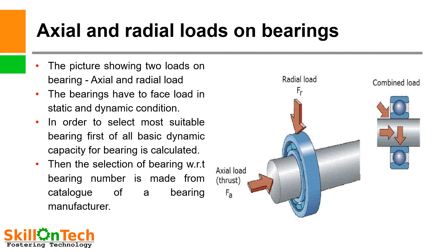Axial and radial loads on bearings. The picture shows two loads on bearings: axial load and radial load. The bearings have to face load in static and dynamic conditions. In order to select the most suitable bearing, first the basic dynamic load capacity is calculated, then the selection of bearing with respect to bearing number is made from the catalog of a bearing manufacturer and procured from a reputed manufacturer.